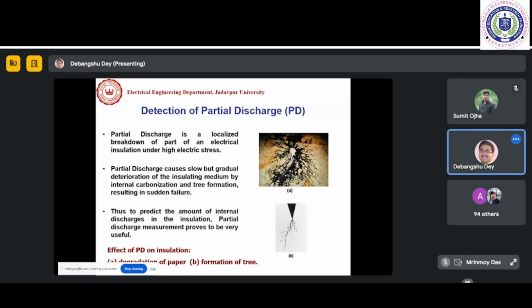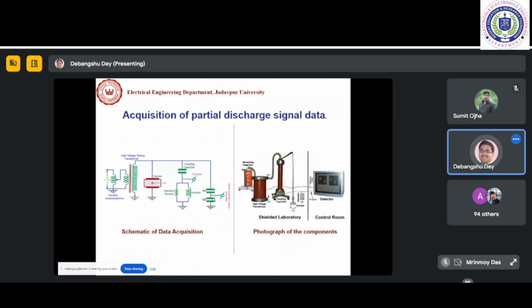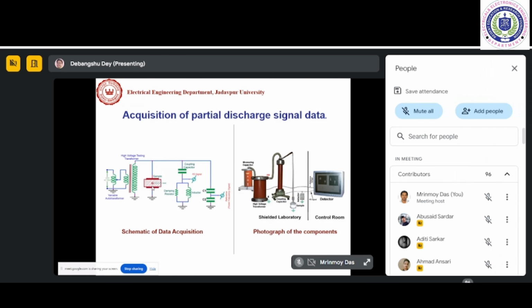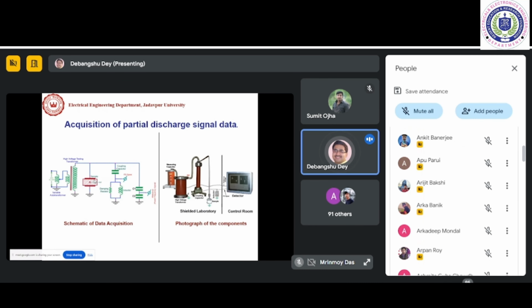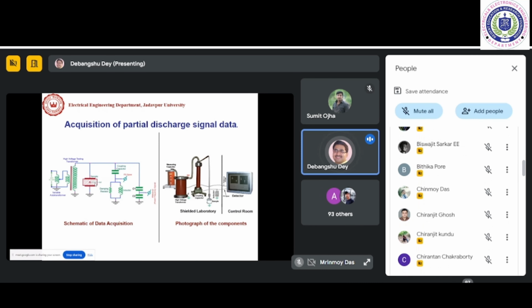Now, this is one kind of data acquisition setup we can use for partial discharge, mostly used in laboratory settings. This is a sample, just showing one insulation with one void. But this sample could represent a transformer, where the transformer insulation is what we are investigating, and the void within that insulation could be our source of partial discharge.